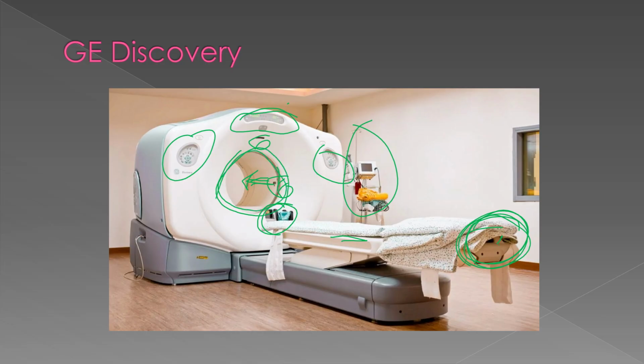The size of this circle is called the bore, and the gantry bore, what I mean is like the diameter in here within the ring, how wide that opening is, that's called the bore. That's important because you know, your bed could handle 450 pounds, but if you have a smaller bore in your camera, then the patient still might not fit.